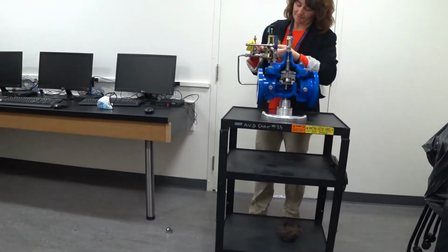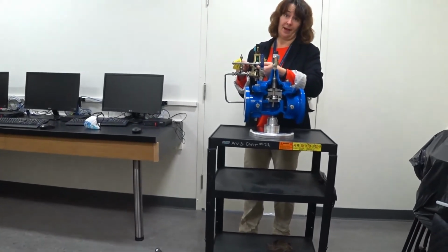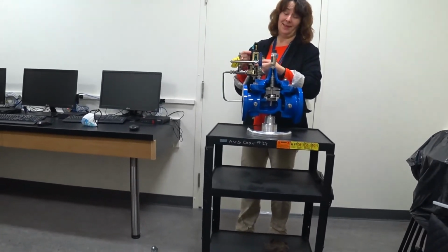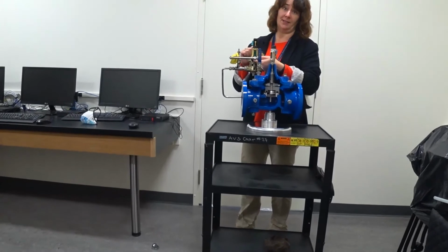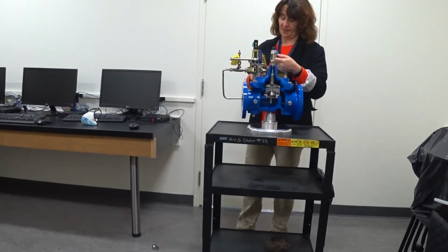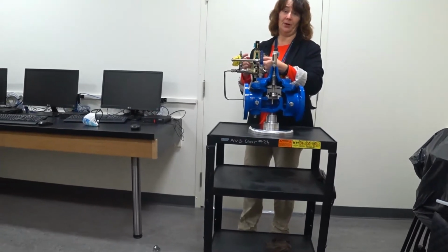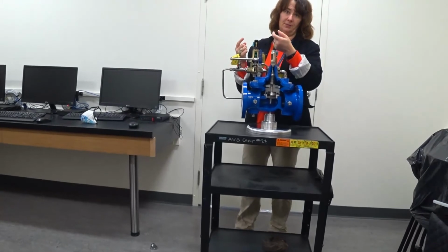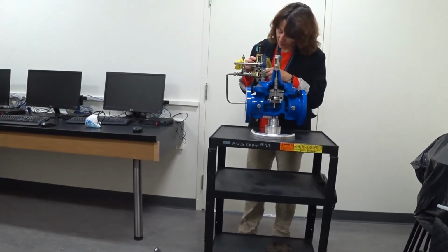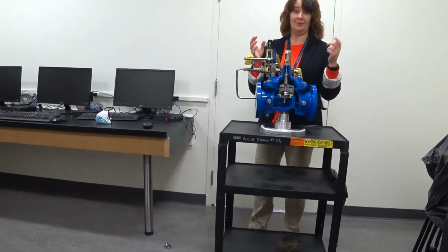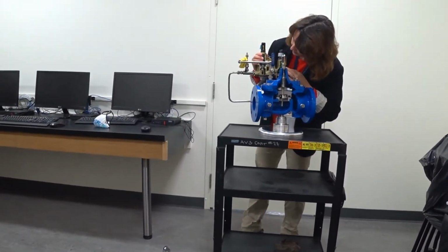And because this is a normally seated valve, when the pressure is higher on the bottom than the spring pressure is set at, so the spring pressure will be set at 100 psi, if you've got 100 psi going into the valve sensing chamber, it will overcome the spring force, lifting the stem, which lifts the disc off the seat and opens this valve, right? Hey, we're open. So we're feeling pretty good about that.